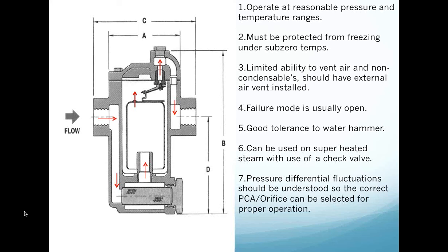Now, I have to say that the inverted bucket steam trap is a very good device, but it has a little bitty, teeny tiny hole right on the top of the bucket where this red arrow is, and that is its ability to vent air. I like to promote an external air vent when someone uses an inverted bucket steam trap, to make sure we can evacuate the air and non-condensables. That way, this particular trap, all it has to do is be good at processing the condensate as it's formed. Failure mode of this trap is typically open.